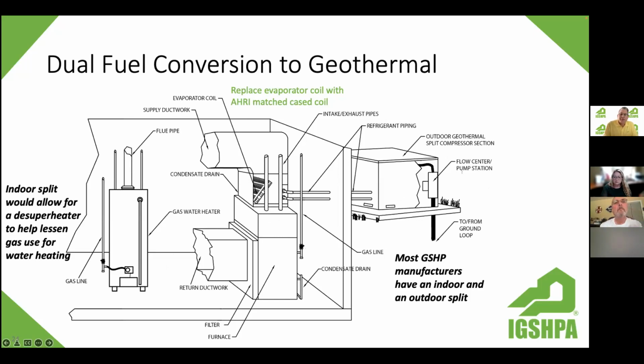But notice the difference here between that first installation I had on the screen with the gas furnace and central air conditioning system. We probably can even use the same refrigerant line piping. So the difference is this outdoor unit. And that outdoor unit then has typically a pump or a pump station, flow center inside. We connect to the ground loop right here, and we're using basically the same setup that we have, but we've converted that home to geothermal now. And because of the low balance point, if you remember that chart earlier on, we're not going to need a lot of backup heat, which means we keep this furnace off most of the time.